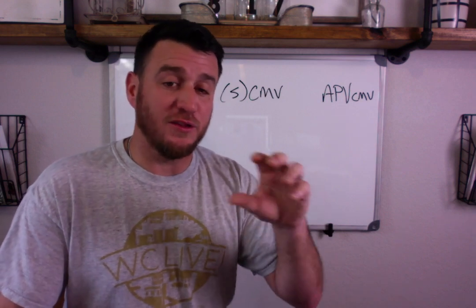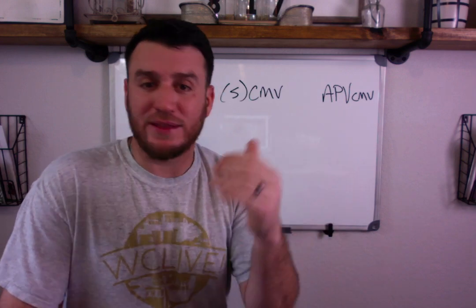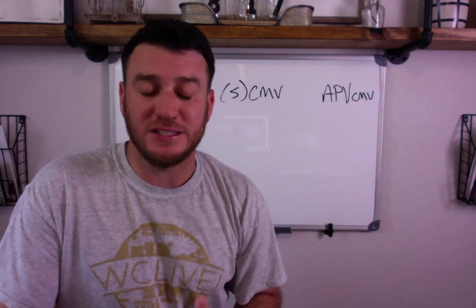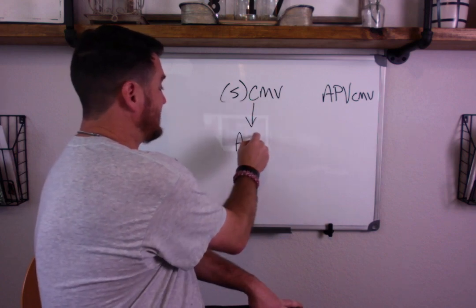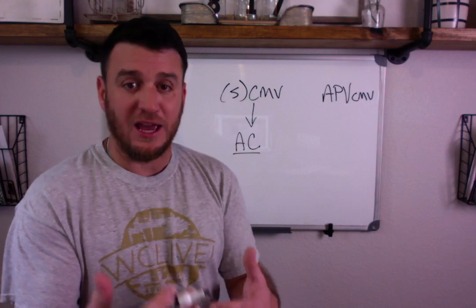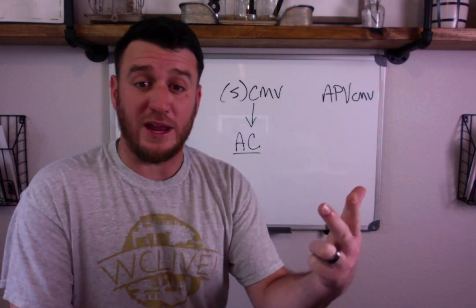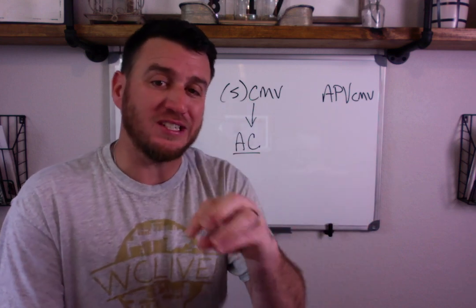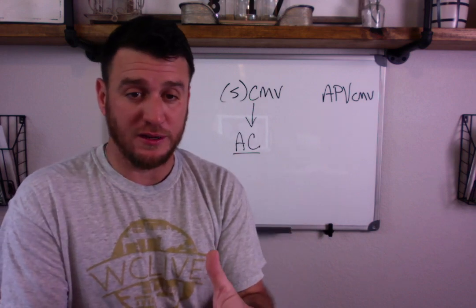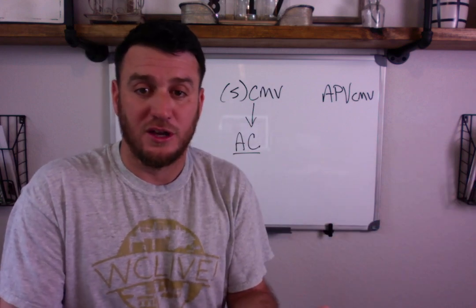What that's telling you is that the ventilator is going to deliver a controlled set of mechanical ventilation — whatever is set is what the vent is going to do. But if the patient wants a breath, the vent will synchronize with the patient's effort. Because this is CMV, every breath is controlled by the vent. This is the same as assist control. In assist control you set tidal volume, flow, and rate; if the patient triggers a breath, the vent delivers that same set tidal volume and flow.